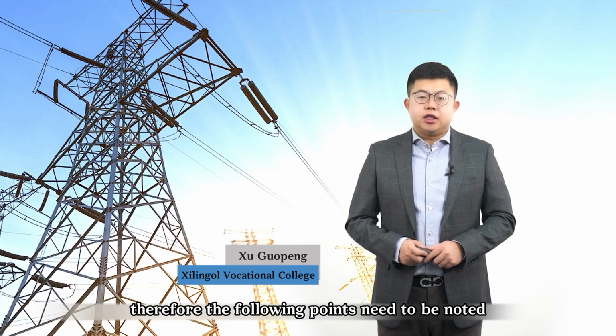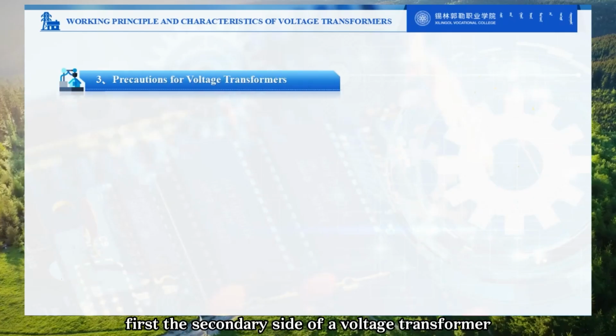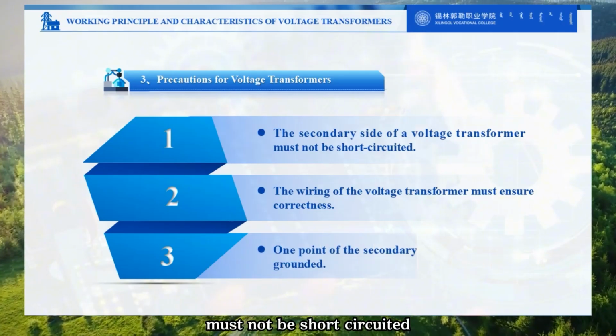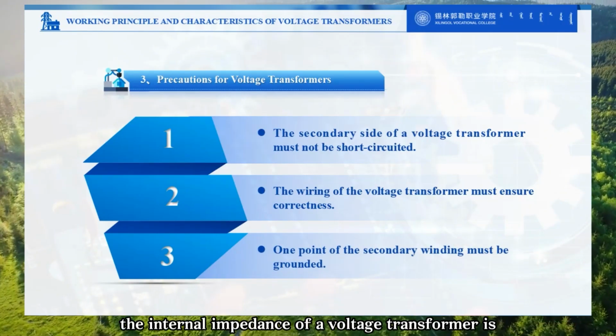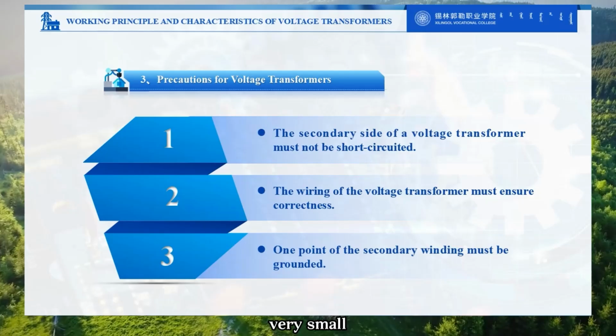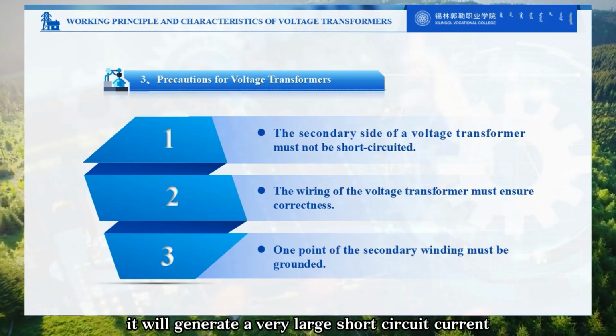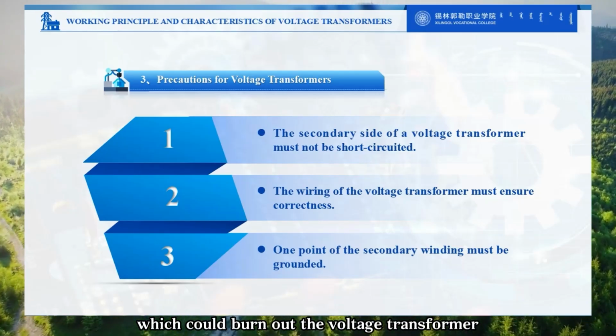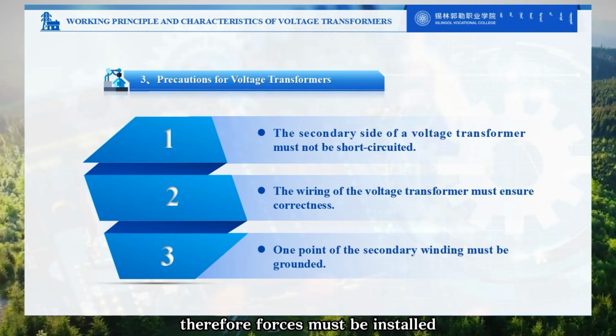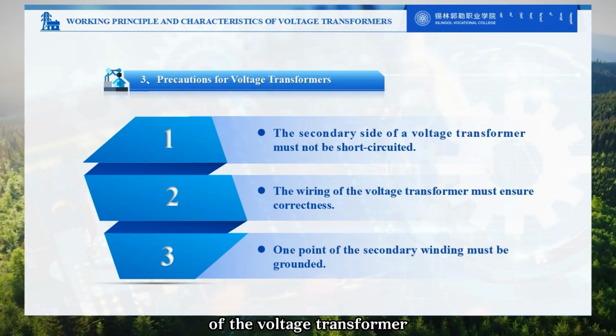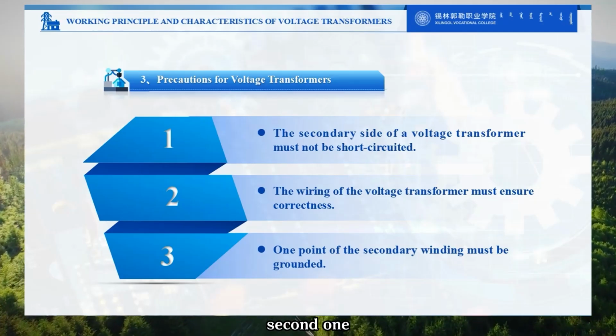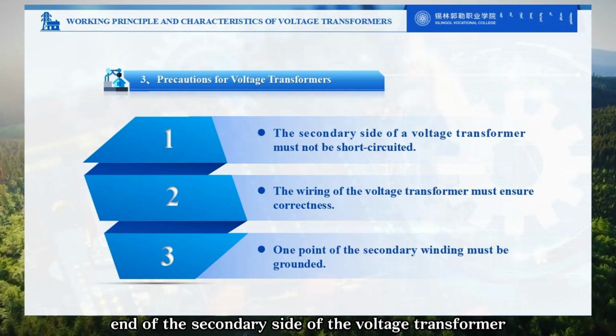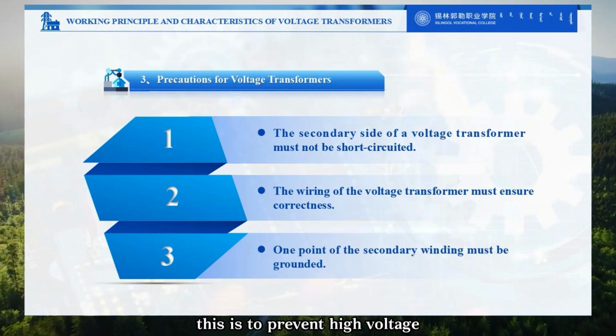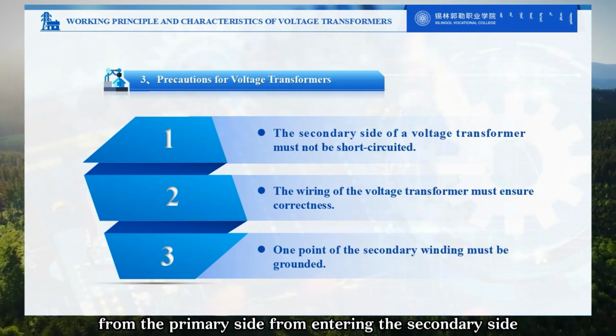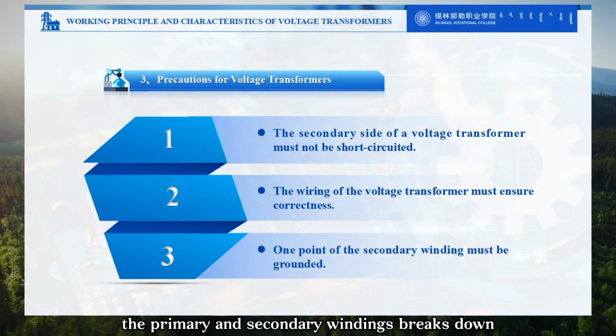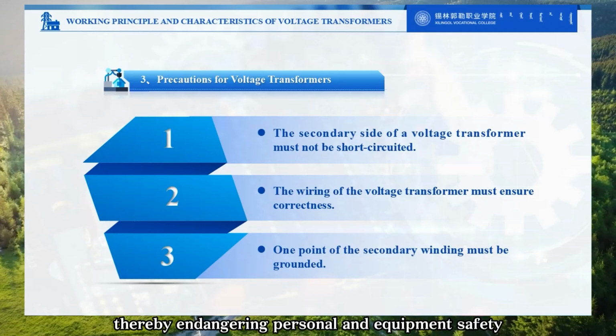Therefore, the following points need to be noted when using voltage transformers. First, the secondary side of a voltage transformer must not be short-circuited. This is mainly because the internal impedance of a voltage transformer is very small. If a short circuit occurs, it will generate a very large short-circuit current, which could burn out the voltage transformer. Therefore, fuses must be installed on both the primary and secondary sides of the voltage transformer for short-circuit protection. Second, one end of the secondary side of the voltage transformer must be grounded. This is to prevent high voltage from the primary side from entering the secondary side if the insulation between the primary and secondary windings breaks down, thereby endangering personal and equipment safety.